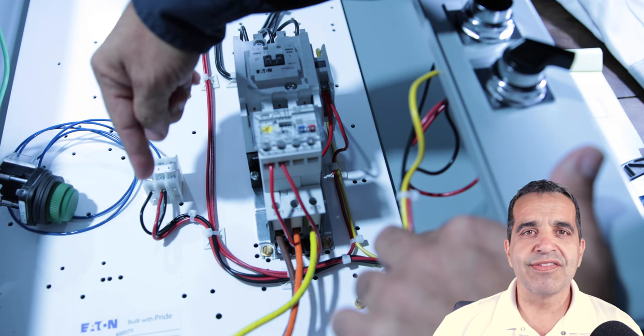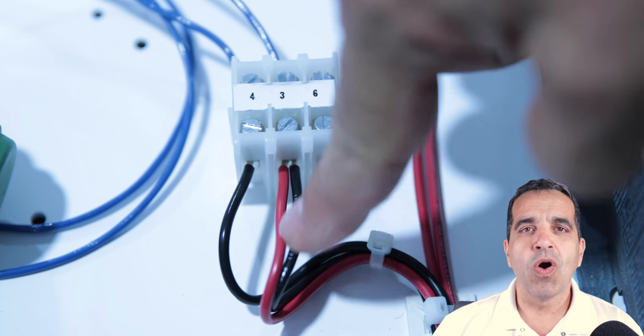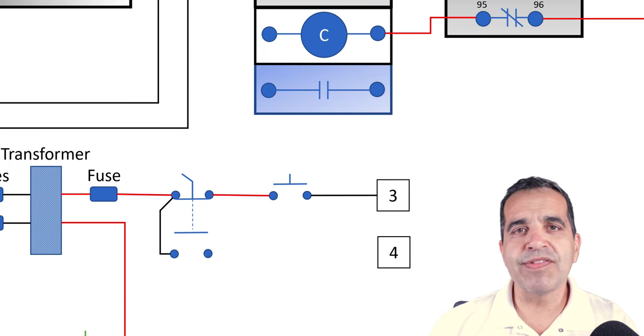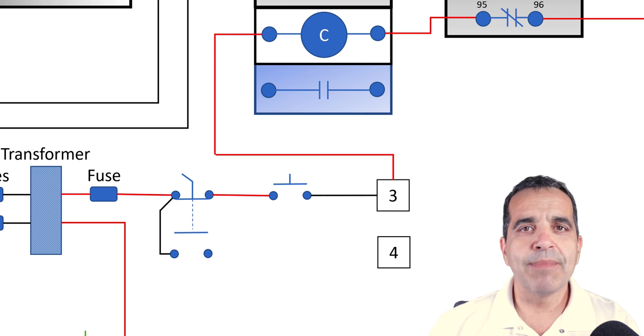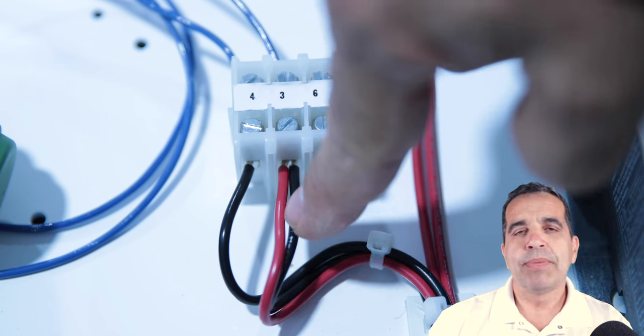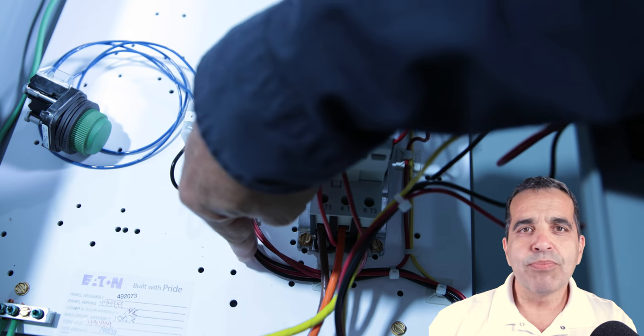It's the black wire coming from our start button to terminal block number three. At terminal block number three, we see a red wire that's jumpered there, and that jumper is coming up to the other side of our coil, finishing our 120-volt loop. But this would only work if we were to push the button and hold the button.